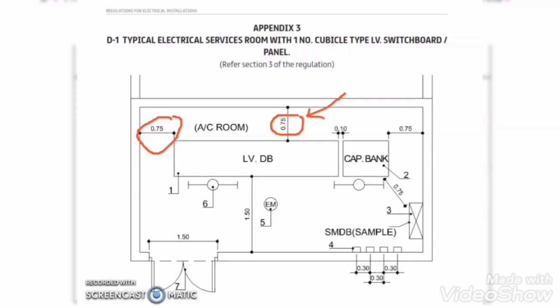The third requirement is that the LV panel front wall must be minimum 1.5 meters away from the front side of the LV room wall. If the distance is more than 1.5 meters it is fine, but minimum we have to maintain 1.5 meters. The LV room door width should also be 1.5 meters.